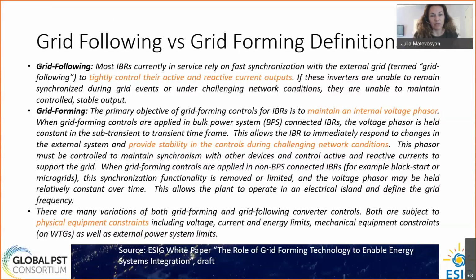For grid forming inverters, the primary objective is to maintain an internal voltage phasor, and when grid forming controls are applied in bulk power system connected IBRs, the voltage phasor is held constant in the subtransient and transient time frame. This allows the IBR to immediately respond to changes in external system conditions and provide stability in controls during challenging network conditions. This phasor must be controlled to maintain synchronism with other devices on the grid and control active and reactive currents to support the grid. When grid forming controls are applied in non-BPS connected IBR, for example for black start or microgrids, the synchronization functionality is removed or limited, and the voltage phasor may be held relatively constant over time. This allows the plant to operate in an electrical island and define grid frequency for the entire island.